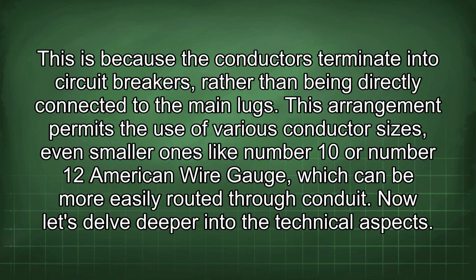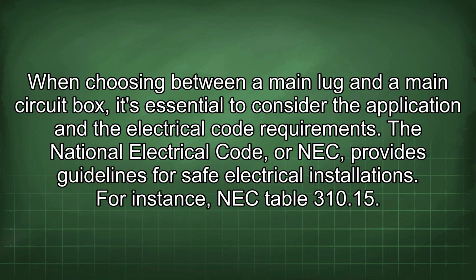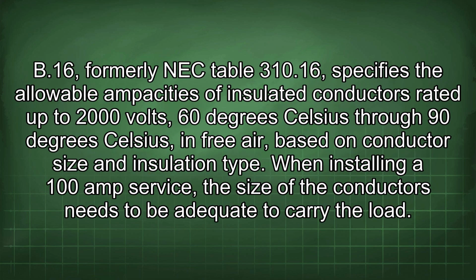Now let's delve deeper into the technical aspects. When choosing between a main lug and a main circuit box, it's essential to consider the application and the electrical code requirements. The National Electrical Code, or NEC, provides guidelines for safe electrical installations. For instance, NEC Table 310.15(B)(16), formerly NEC Table 310.16, specifies the allowable ampacities of insulated conductors rated up to 2000 volts, 60 degrees Celsius through 90 degrees Celsius, in free air, based on conductor size and insulation type.